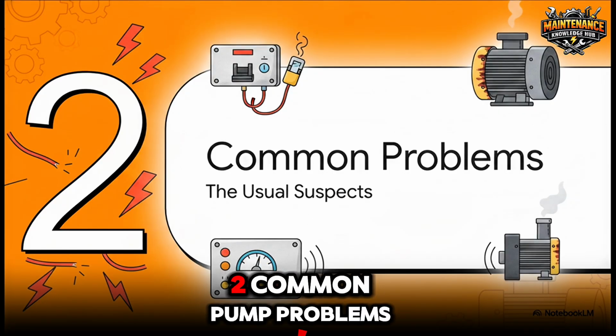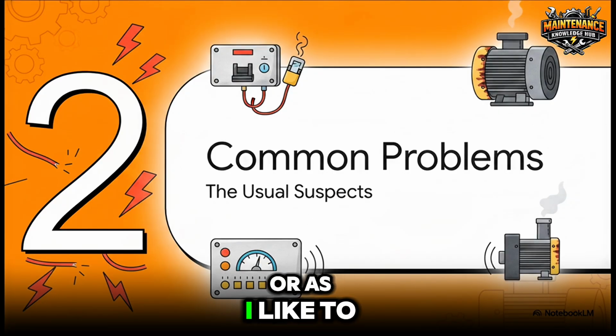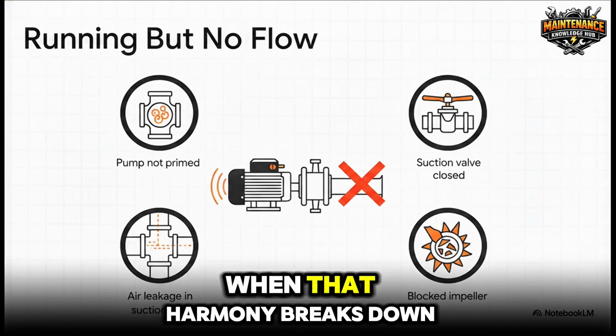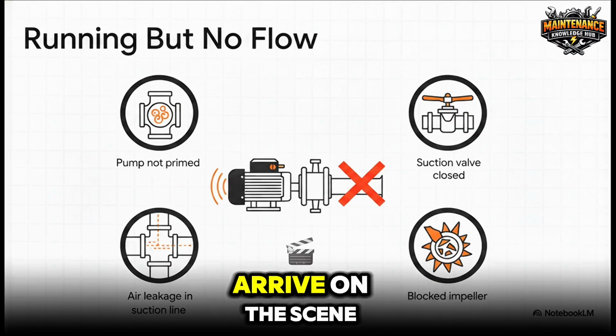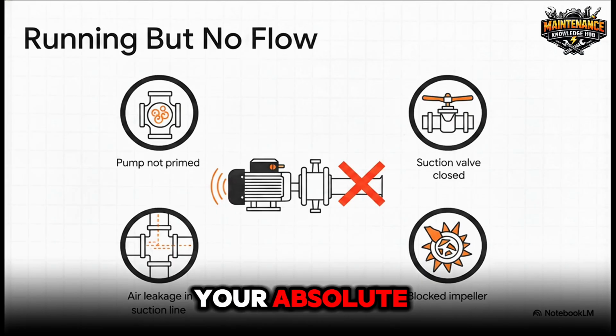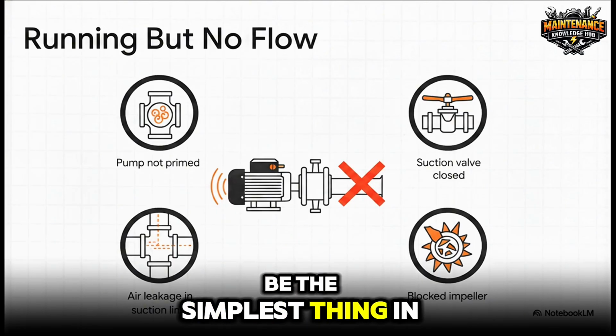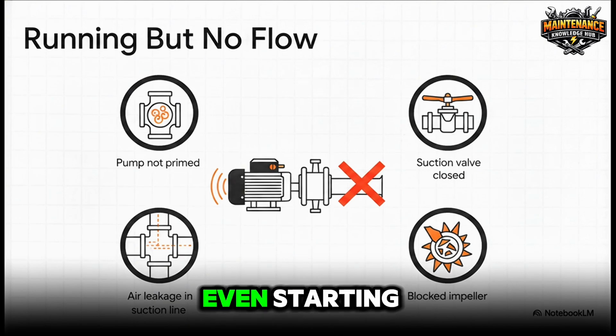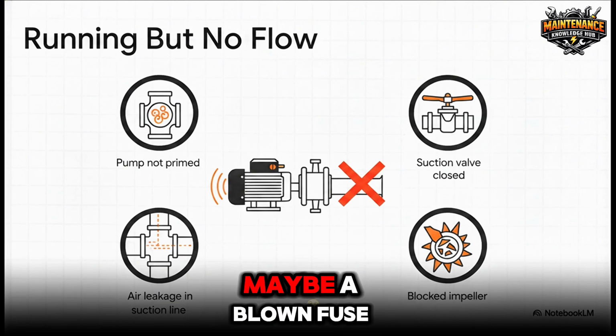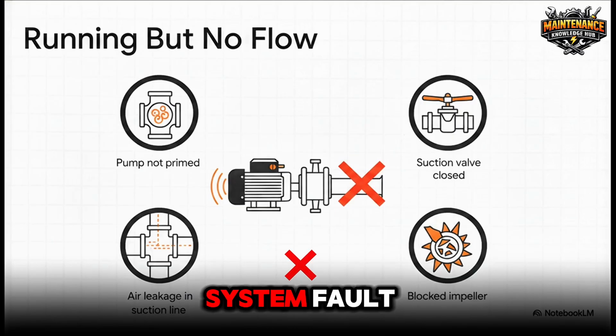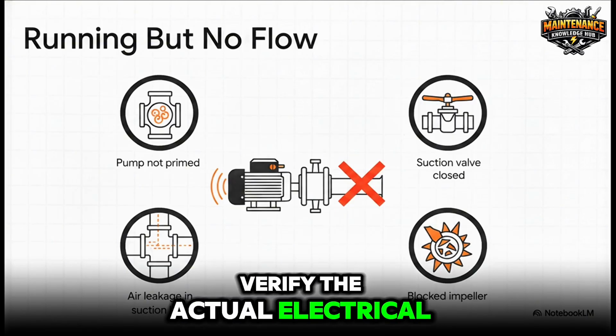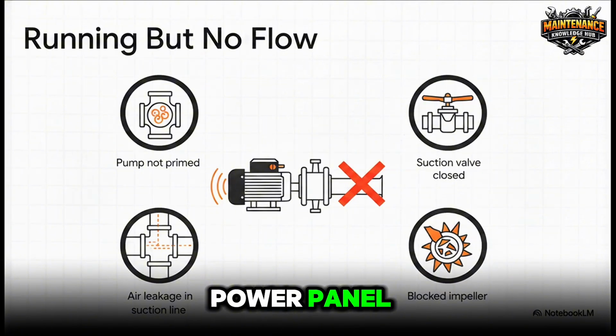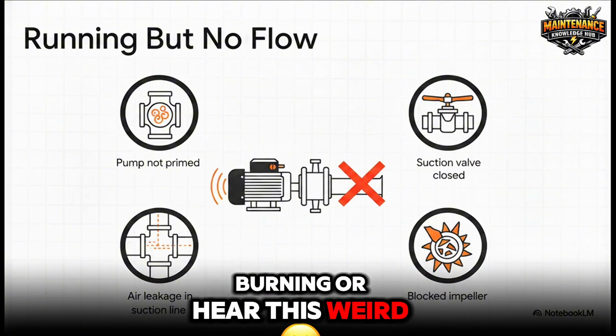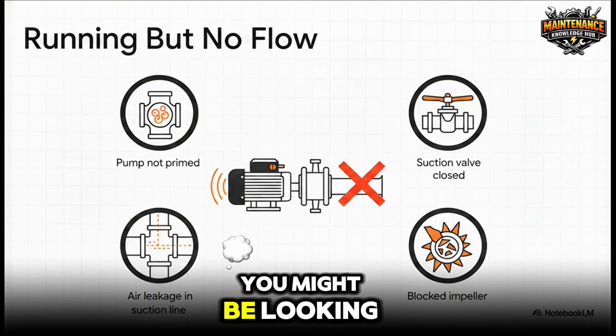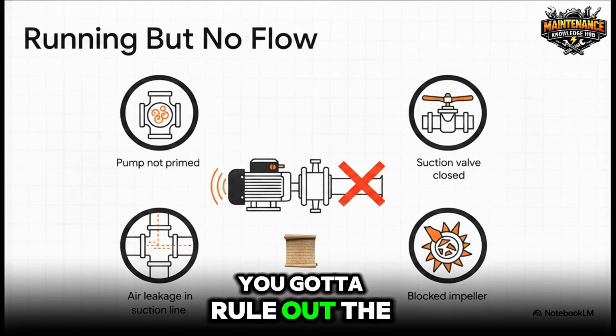Moving on to Section 2, common pump problems, or as I like to call them, the usual suspects. So what exactly happens when that harmony breaks down? Well, when you first arrive on the scene of a malfunctioning pump, your absolute first check should actually be the simplest thing in the world, the power. Is the pump even starting? If not, check for a tripped breaker, maybe a blown fuse, or some kind of control system fault. Always verify the actual electrical supply voltage at the main power panel. If you smell something burning or hear this weird humming noise but nothing is moving, you might be looking at a motor winding failure. You gotta rule out the power first.